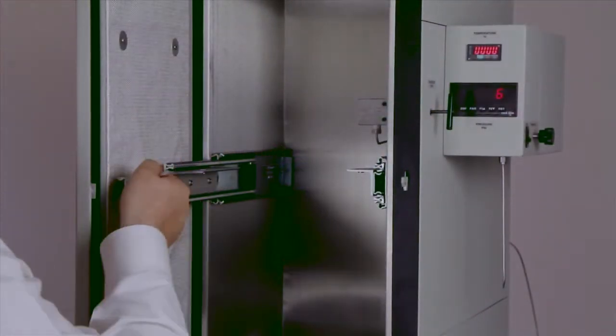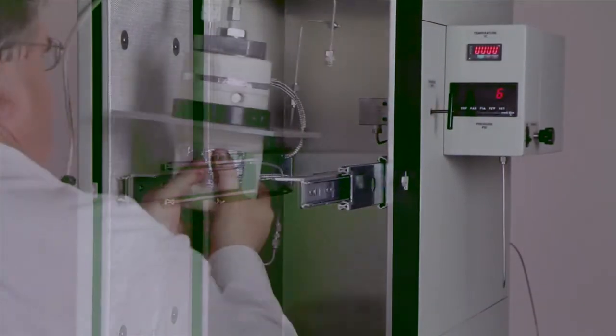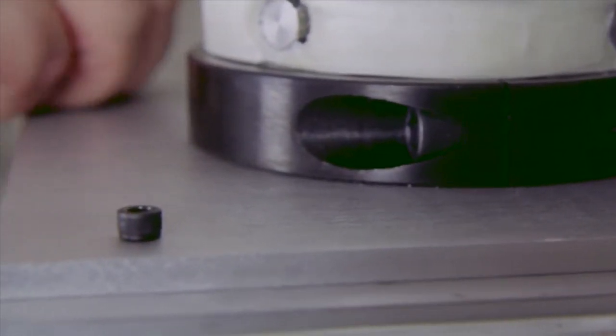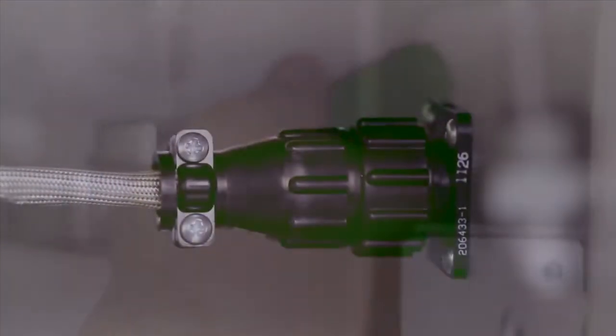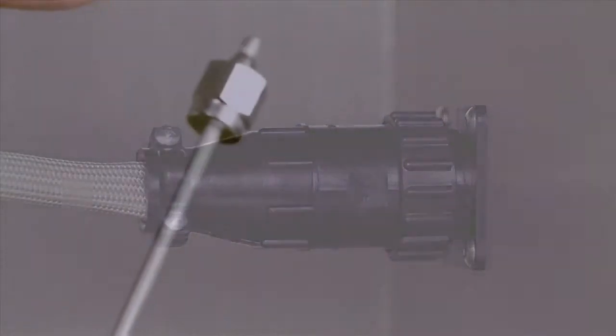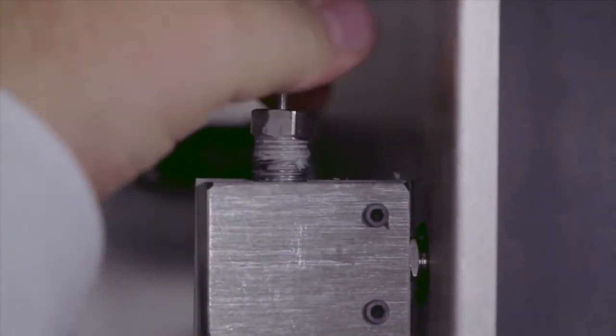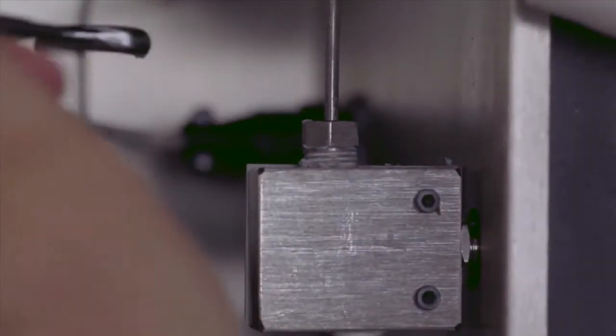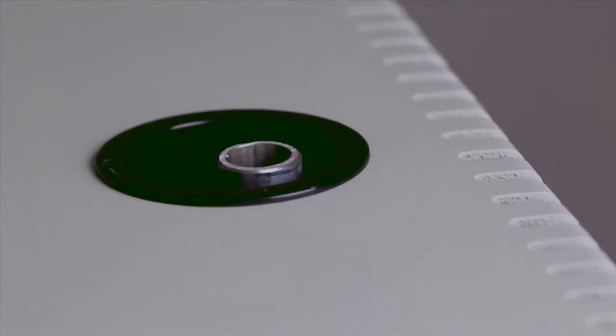Now the vessel assembly is installed into the SFT-150 cabinet. Insert and tighten the 4 Allen screws. Now make the connections to the RTD, heater power, CO2 inlet, and CO2 outlet. Ventilation for the rupture disc outlet, located on the top of the SFT-150, must be provided.